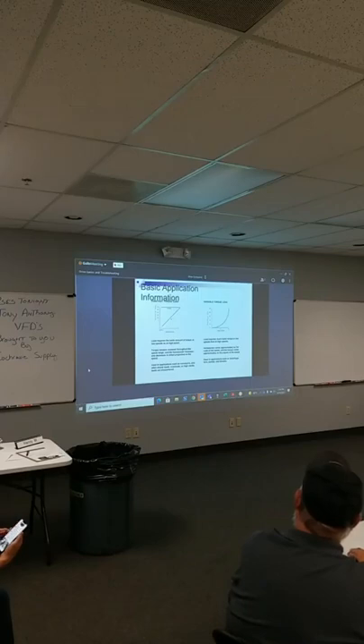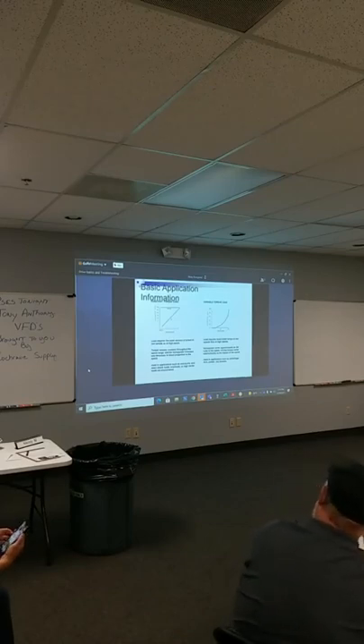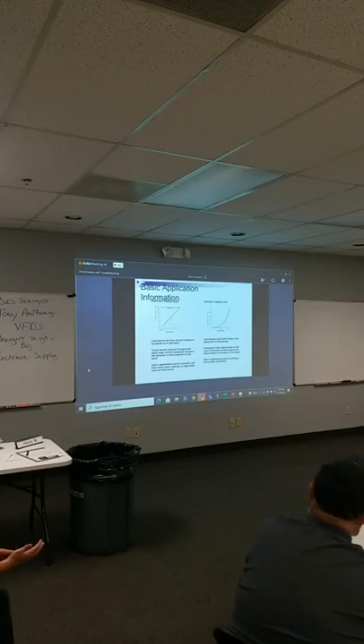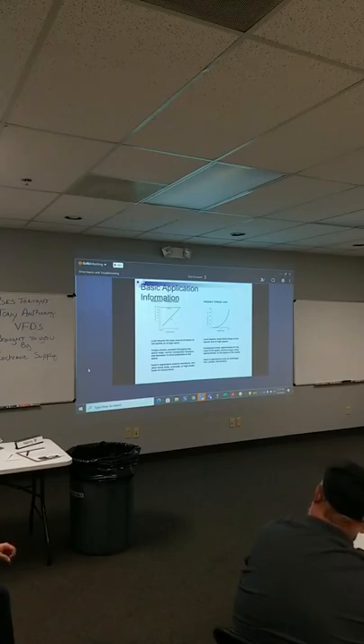If you need to convince a customer that he needs drives, we have software that can show that payback analysis. It does a very good job of showing it with charts and graphs and all the bean counting. We actually had an ID fan at a steel mill, and there was rebate money on the line from the state, and the state required some kind of analysis to show the potential savings. We used our software package, which is free, and sent that to them. They accepted it as the pre-project analysis. So it's very powerful, very good software. It does its job well.